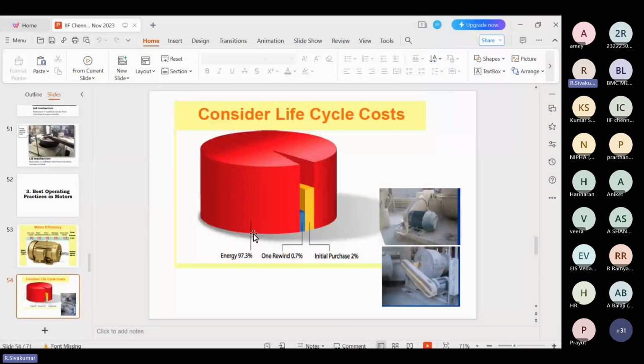This picture says somewhere around 97.3, but practically 95% of the total lifetime cost is the energy cost, and the investment cost is only 3 to 4%, and 2 to 3% is for winding, rewinding, or maintenance activities. So in the lifetime cycle cost of any motor, pump or equipment, energy is the major predominant element. Whenever we purchase a new system or motor, kindly consider an energy efficient motor. For example, if a machine is running for 20 hours in a day, better you consider a higher efficiency motor, IE3 or IE4, instead of IE1. Suppose the motor is running for 1 or 2 hours in a day, you may go with IE1.